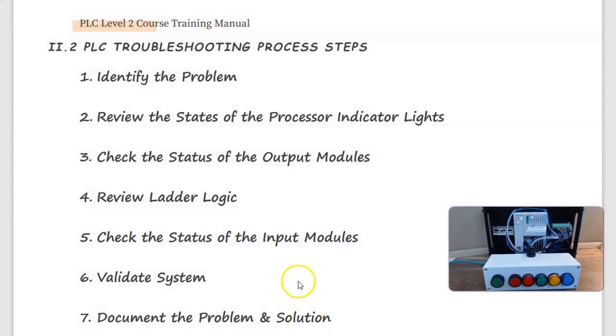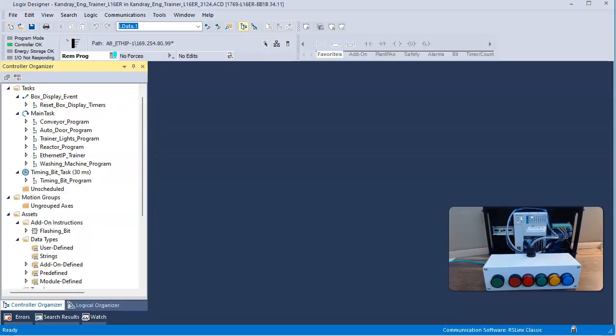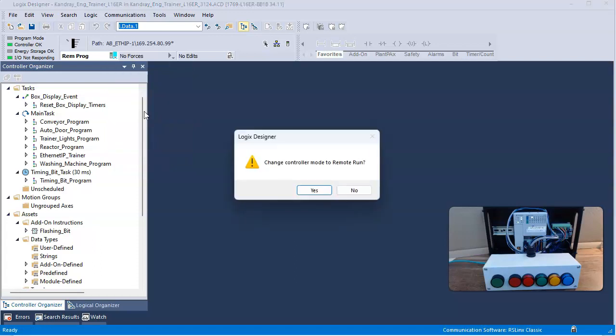We traced that fault using Logix Designer to the IO, and we identified that we had a problem with the IO module. We replaced that IO module and then we attempted to place the PLC into run mode.